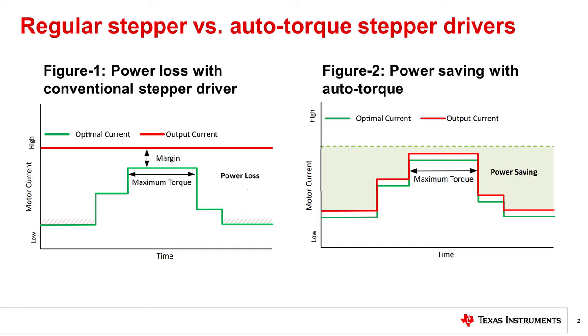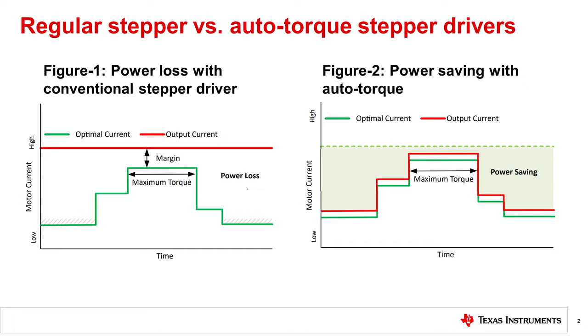In applications where the peak demand for load torque is only for short durations, the efficiency improvement could be as high as 75%. The integrated auto torque feature does not require any external sensor. Instead, by monitoring the power delivered to the motor, it generates an internal signal which linearly varies with the load torque.